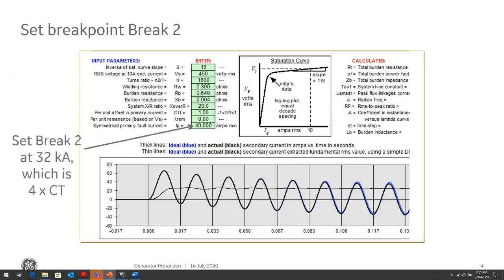And I might even want to go lower because even 40 might be a bit high. So I go about 4 times CT, which is 32. So some margin from your maximum short circuit current that you want to set it at. This could be 70 to 80% margin. Again, this depends on experience, on the person who's doing the settings, and so on.